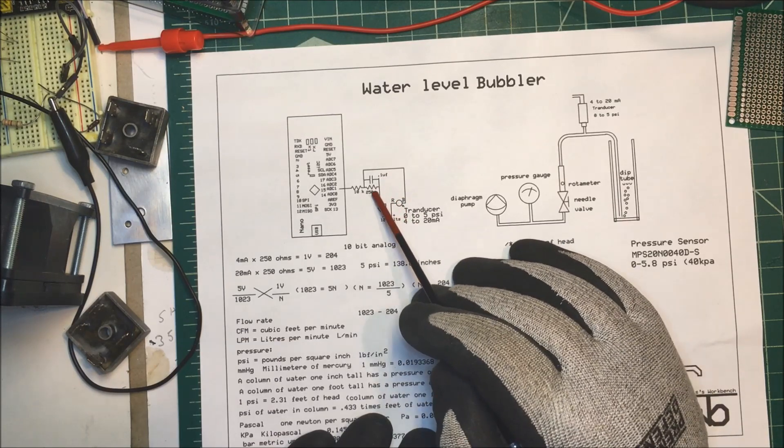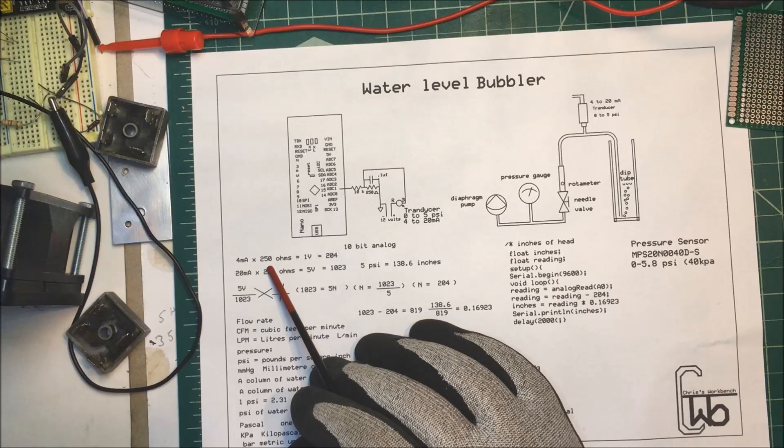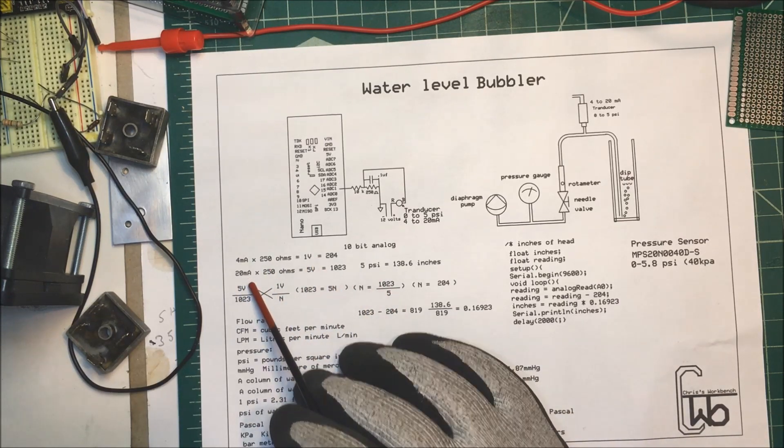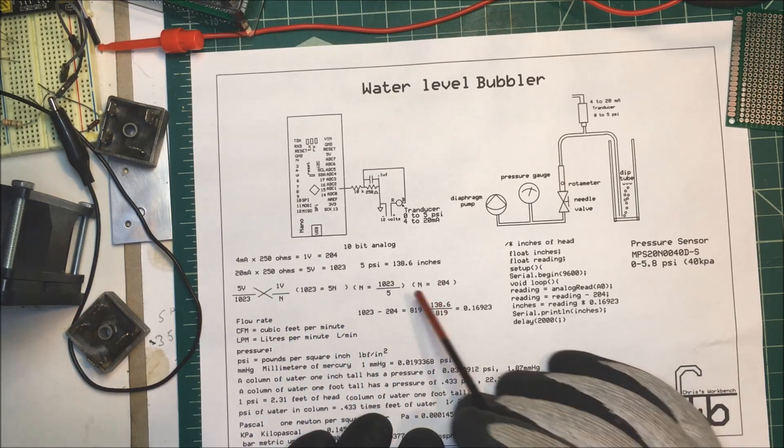Now, if I put four milliamps into a 250 ohm resistor, I get one volt out. And if I use 20 milliamps into 250 ohm resistor, I get five volts.